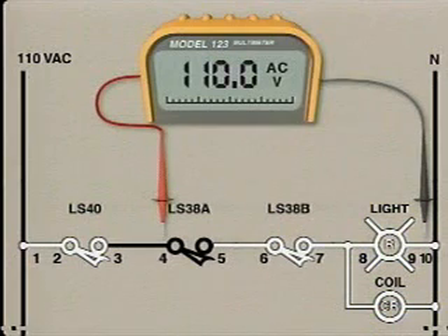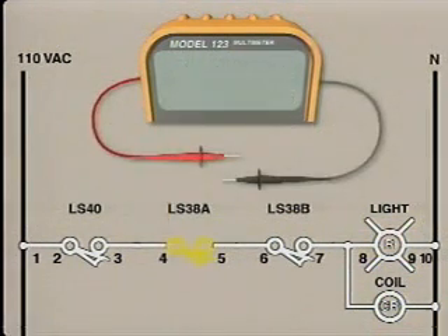Reading full line voltage at test point 4 tells the electrician that the voltage at test point 3 is also present at test point 4. This eliminates the wire between the two test points as a possible cause of the problem. The only remaining possibility is that the open in the circuit that's causing the startup problem is between test point 4 and test point 5, which is the limit switch LS38A. This switch should be closed. However, it appears that the limit switch is open.